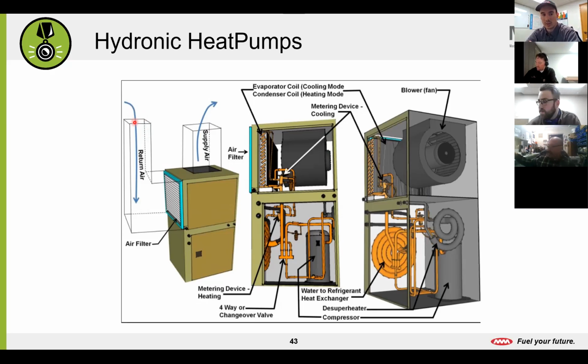Typically how the system would work, let's say, for example, this system here is in cooling. We would have 75-degree air go over this coil. We have cold refrigerant running through our refrigerant coil, which would be this evaporator coil right here.